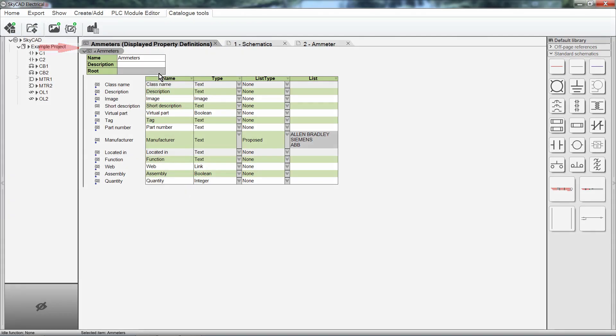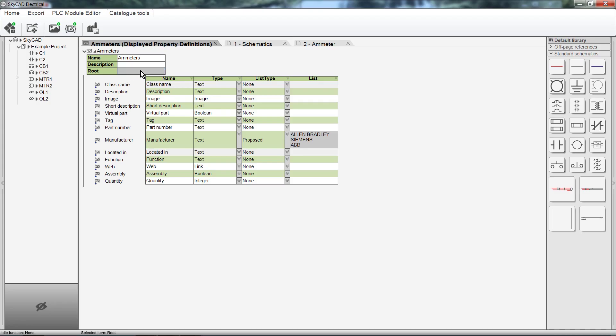Let's define a root. This is the tag a component will naturally adopt when you add it to a drawing. Remember that for motors, the default root is MTR. So for ammeters, I'll call it A. The first ammeter I'll add to my project will be A1, the second A2, and so on. Have a look at the properties and see if you'd like to add any that would be relevant to the new class. For an ammeter, I should add properties such as Size, Voltage, Current, and Scale.